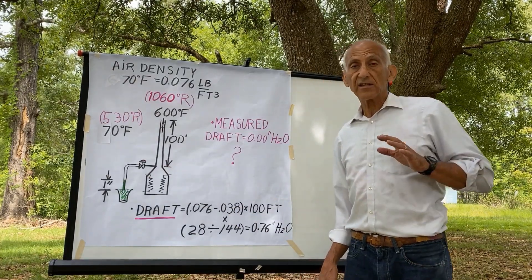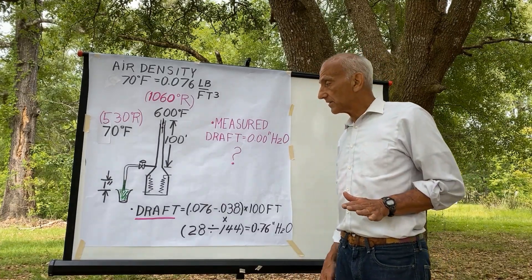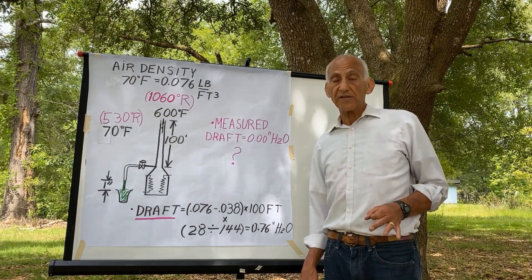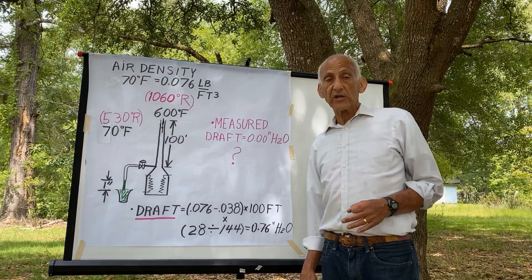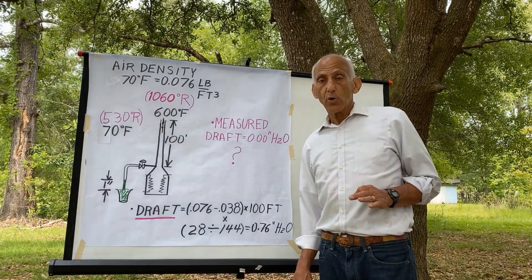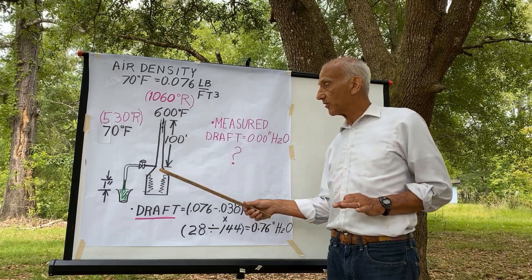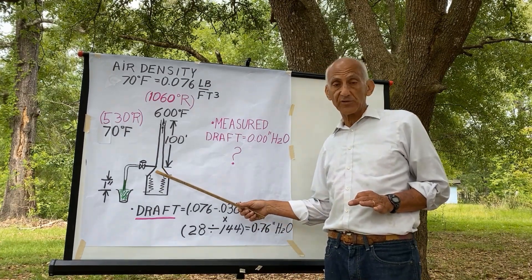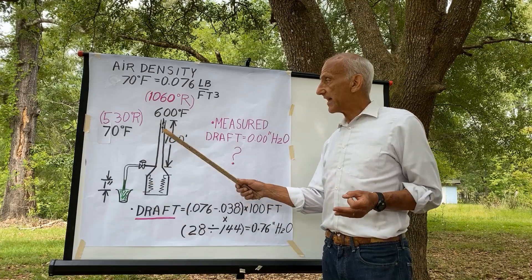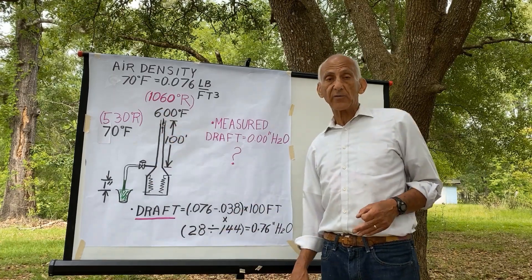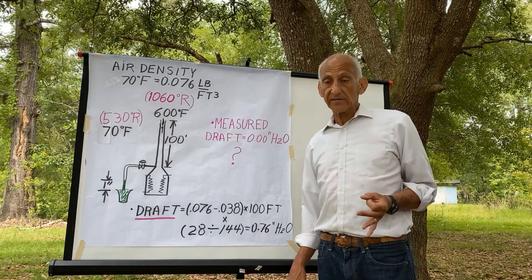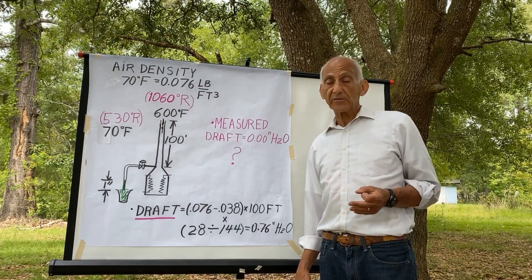He said that since the fuel being burnt is three percent sulfur fuel oil, the evolved fumes are rich in sulfur dioxide, which is very dangerous. Therefore, we are not allowed to run with a negative draft or a positive pressure below the bottom row of convective tubes as a safety item. And since we lack draft and the stack damper is wide open, the only way we can get more draft is to diminish the fuel firing rate, but as we do that we have to cut back on crude.